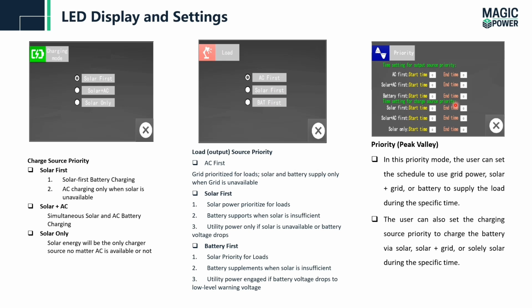In the priority setting, in this case, basically it is designed for those where the prices are not fixed. For example, during the peak hours the prices are higher, and during the off-peak hours the prices are lower. So we can set the time, for example the peak hours are from morning 8 to 10 p.m. During this time, if the prices are high, we use our energy storage to feed the load. But if the prices are lower, from 10 p.m. to 8 a.m. in the morning, in this time we feed the load and charge our battery. So we can use the battery energy during the peak hours. So these are the settings for the charging and discharging of the battery.